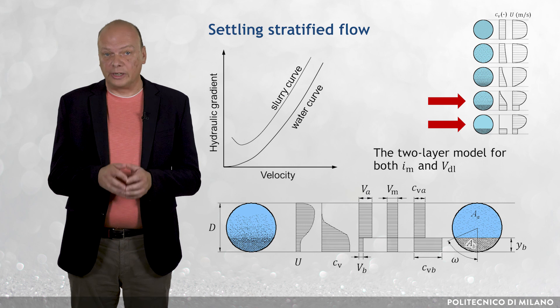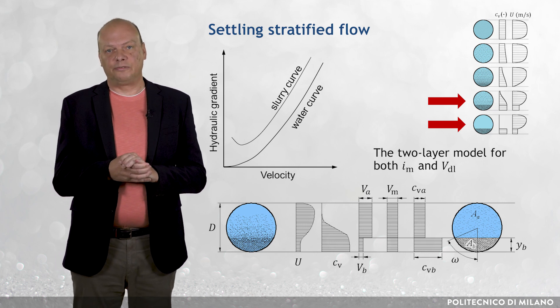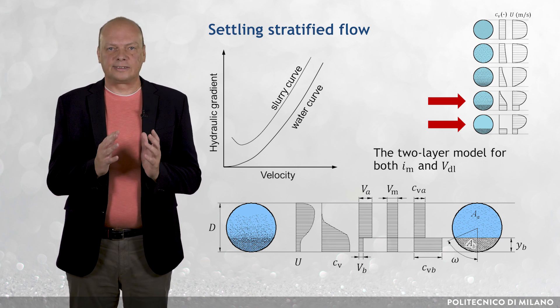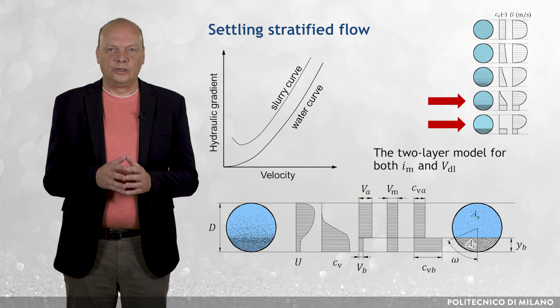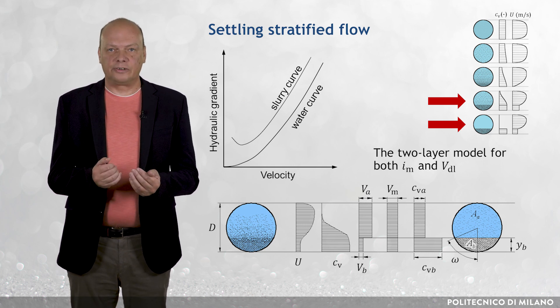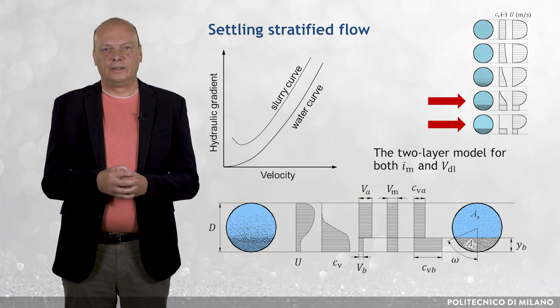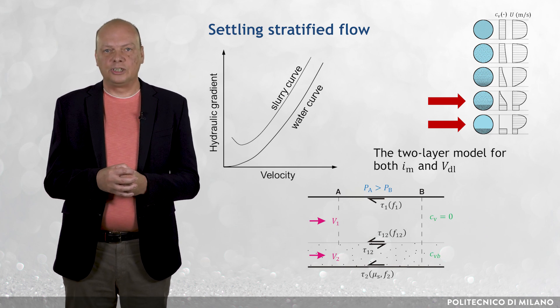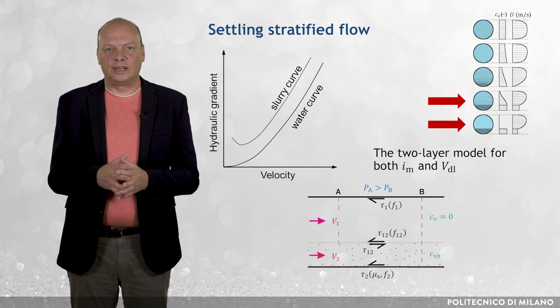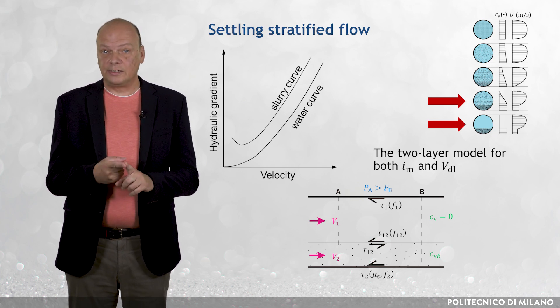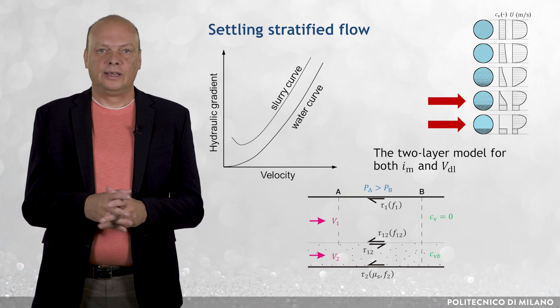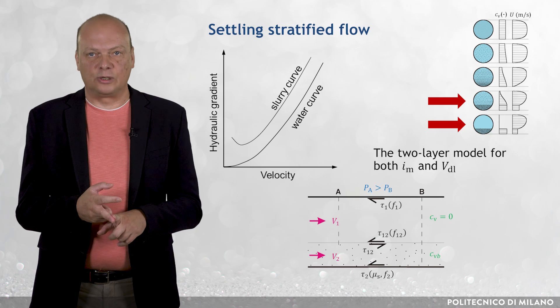Layered models, such as the two-layer model, are applicable to fully stratified flows and partially stratified flows of settling slurries. The model simplifies the internal structure of flow to a layered structure and considers mean values of flow quantities in each layer. A layered model formulates force balances for each individual layer, and besides the frictional hydraulic gradient, it solves velocities and thicknesses of the layers. Note that layered models are also applicable to complex non-Newtonian flows which tend to stratify due to the presence of coarse particles.